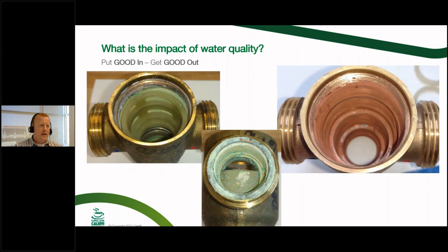All right, now last but not least, water quality. Oh my gosh, we talked about water quality a little bit before with heat exchangers. Water quality is something that is going to plague literally every single component in a domestic hot water system, and the most common one to really take the heat for it is the mixing valve. If you've got hard water, you're going to know it. If you've got nasty water, you're going to know it. Chances are you've worked in that municipality before, you've worked in the building before, you've changed out faucet cartridges and shower valves and cartridges and everything like that, and you know it's going to go bad.